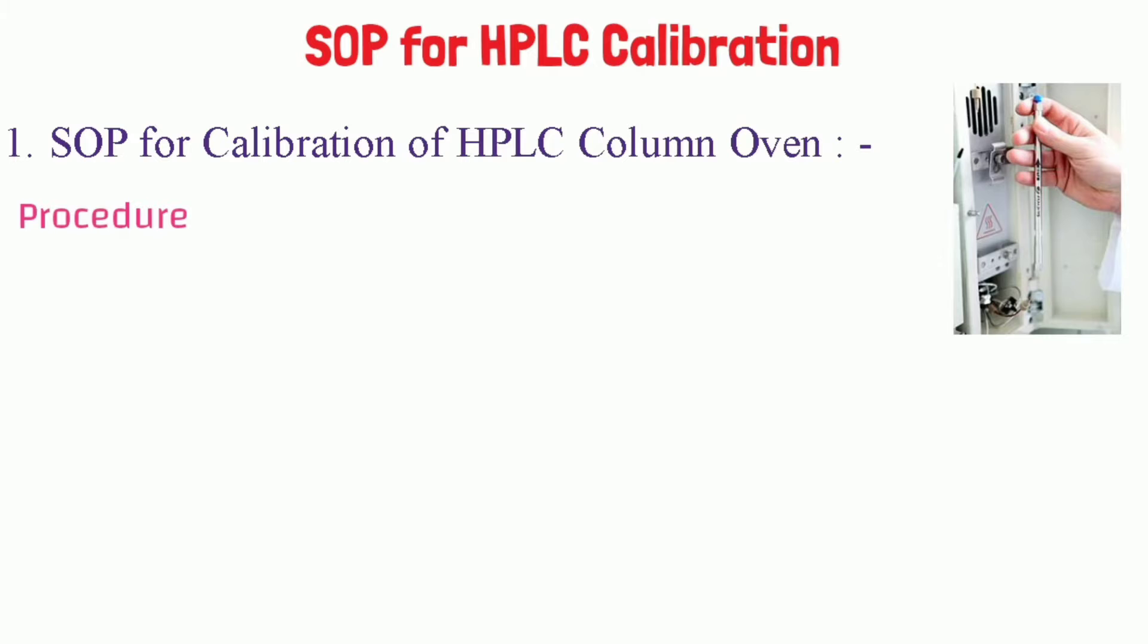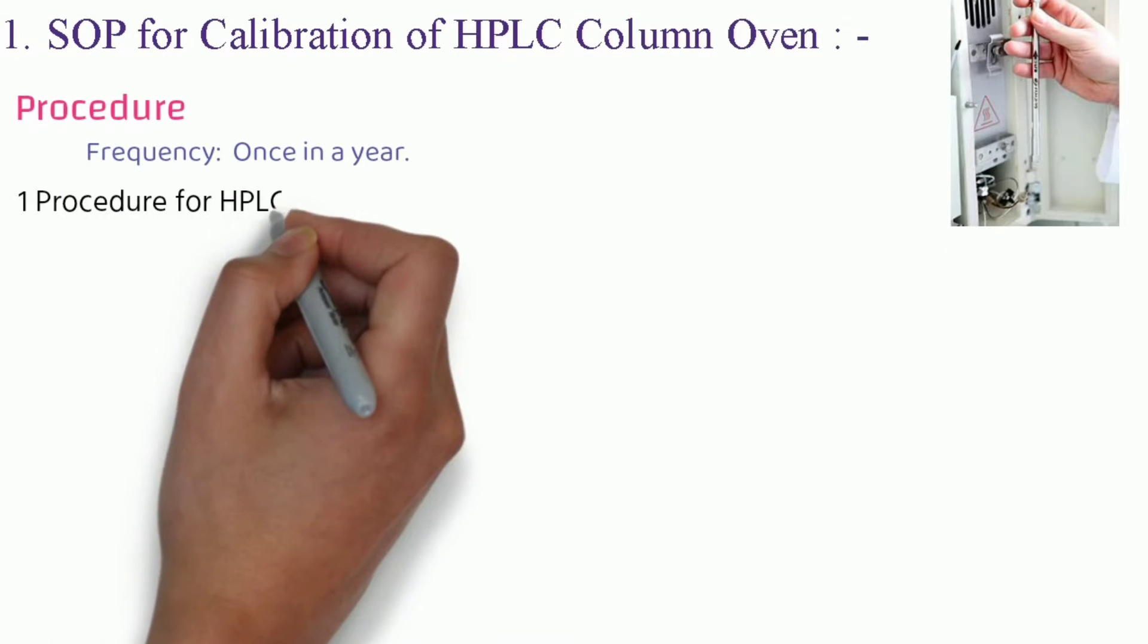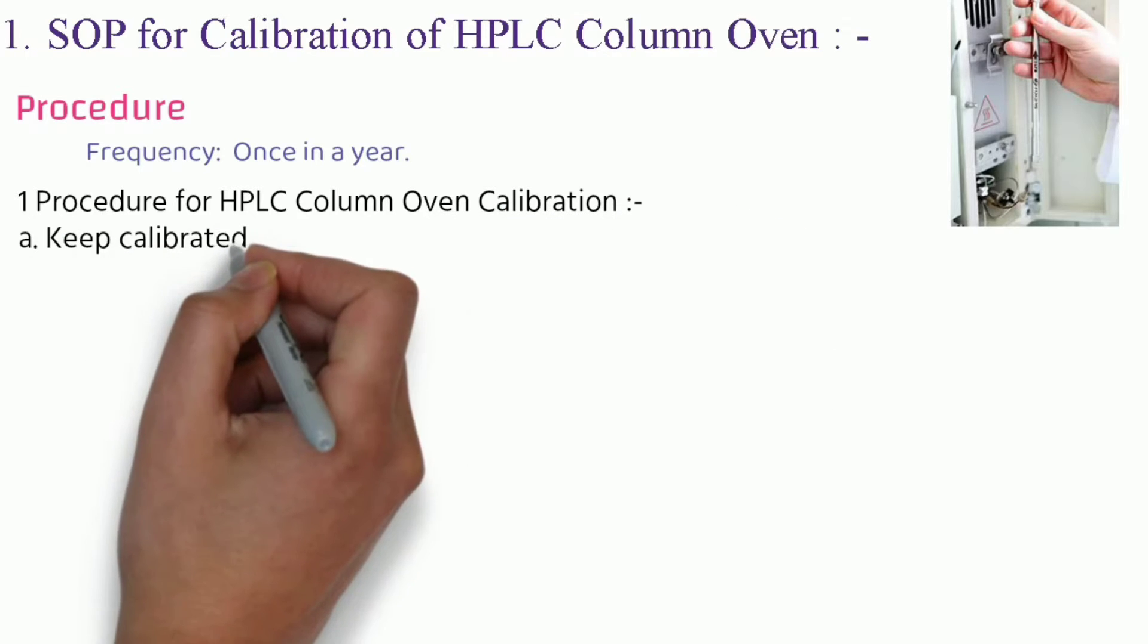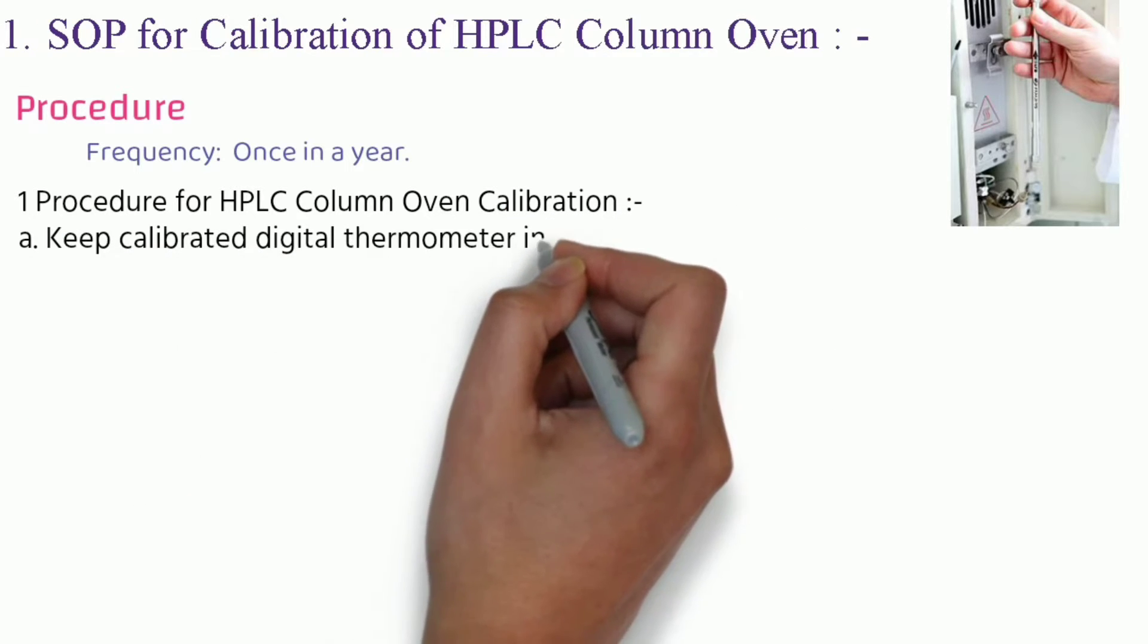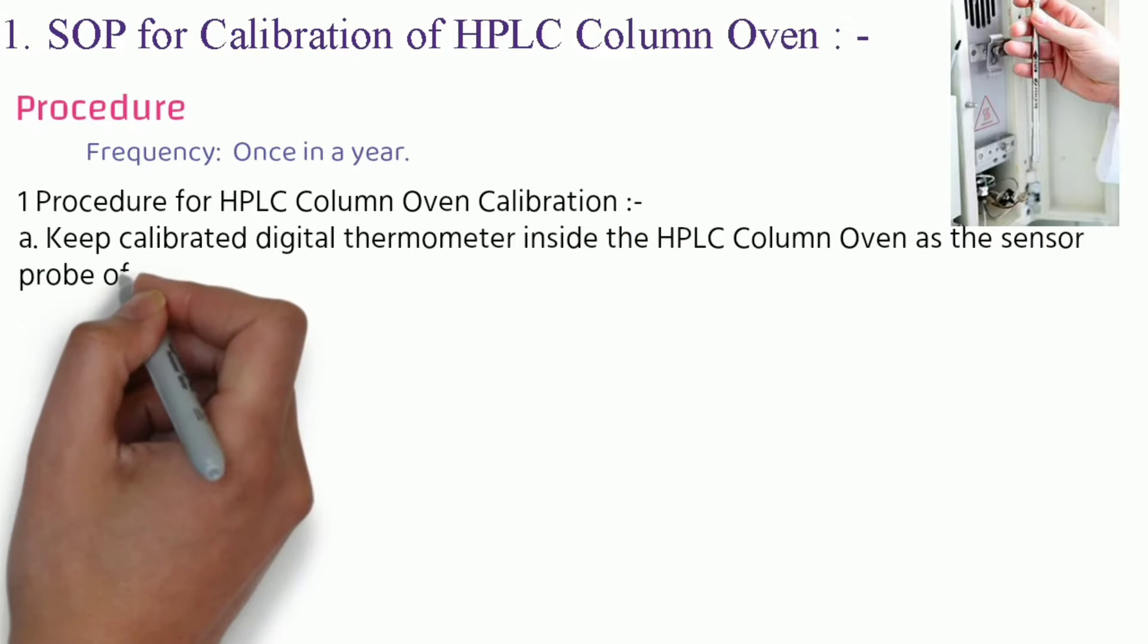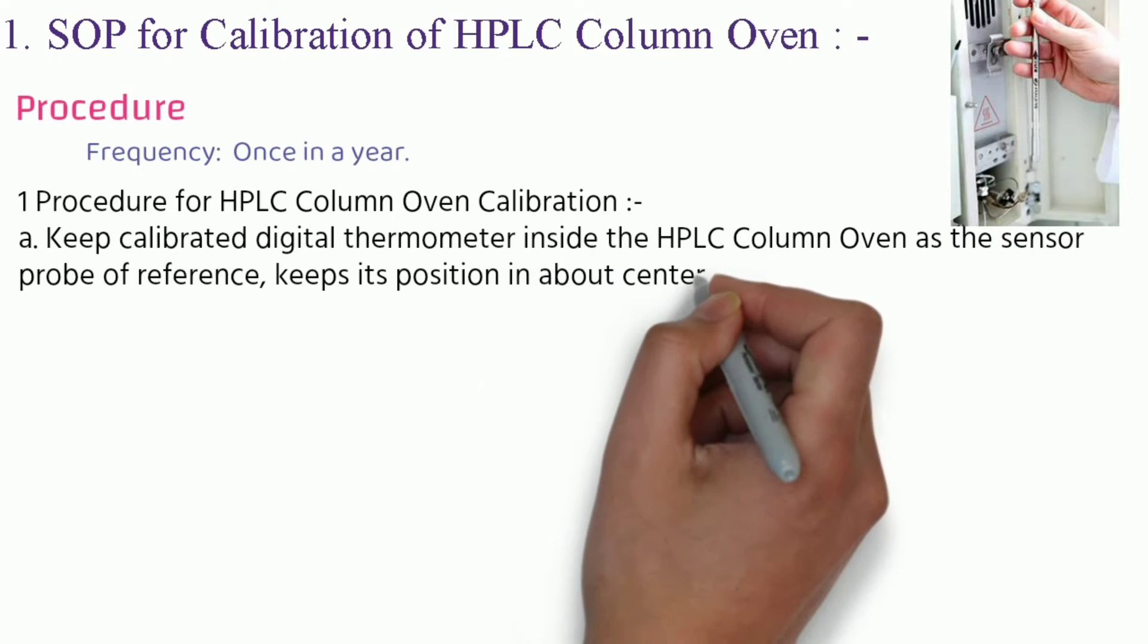Procedure: Its frequency is once in a year. Procedure for HPLC column oven calibration: Keep calibrated digital thermometer inside the HPLC column oven as the sensor probe of reference. Keep its position in about center of the oven chamber.